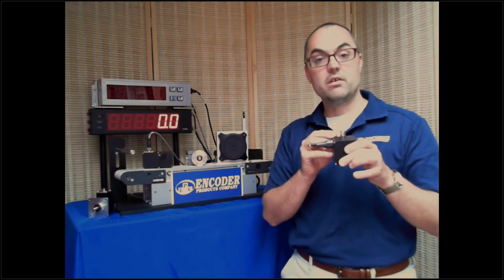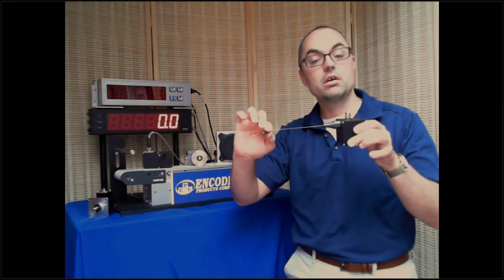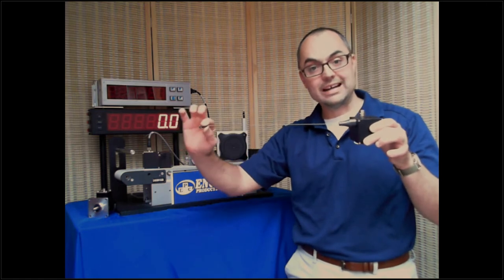This encoder puts out 500 ticks or pulses per inch. So I've got a resolution here of two thousandths per tick mark of an inch of travel. So I can very accurately measure with this encoder the linear distance.